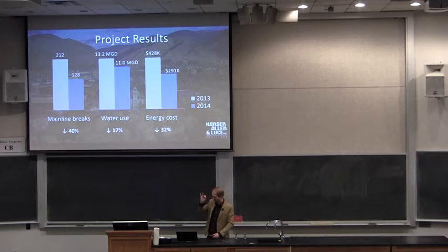So if you can think about it, they have old pipes, water is leaking out all over the place. If you reduce the pressure in the same amount of time, less water is going to come out of those pipes. And so they actually saved this amount of water, which actually was added to the energy savings. Because again, water lost out of the system is energy lost out of the system. So that was a bonus 17%. Plus, they're using less of another scarce resource, water.